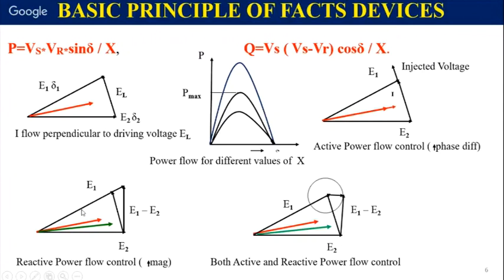If you boost the voltage at either of the ends, sending end or receiving end, that will change the magnitude of the voltage, which will in turn affect the reactive power flowing through the line. This principle is used in STATCOM. That is, you can change the voltage profile, which will give reactive power flow control. These two principles are used where there is control of both active power and reactive power. So this principle is used in UPFC.